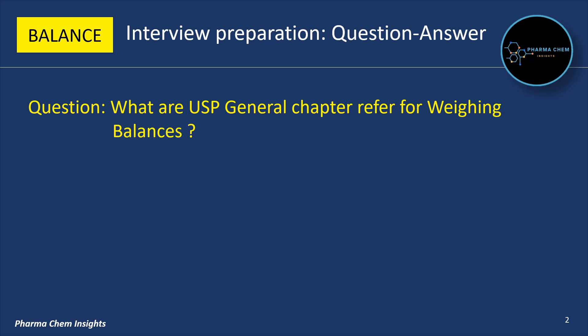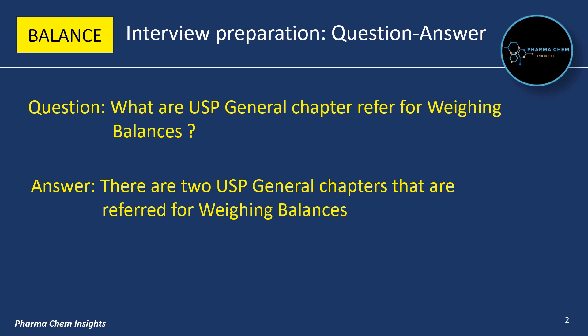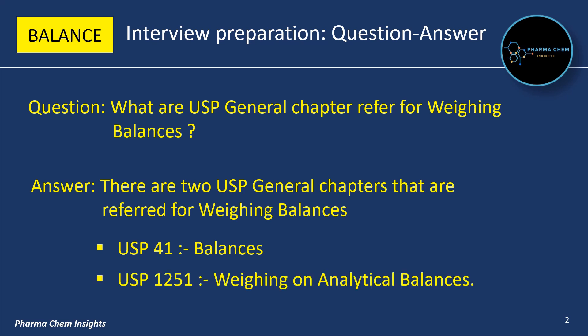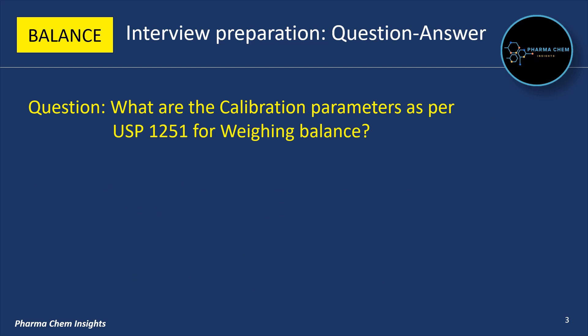First question: what are the USP general chapters referred for weighing balances? There are two USP general chapters that are referred for weighing balances. First is USP 41 Balances, and second is USP 1251 Weighing on Analytical Balances.